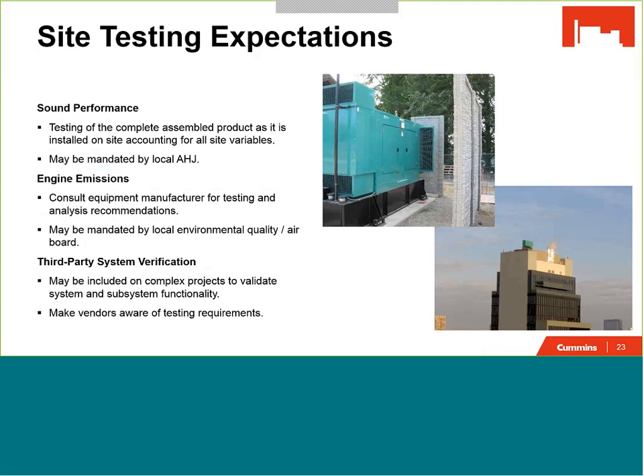Some other on-site testing expectations or types that we see include things like sound testing. Sound testing is often verified on-site if there is a local requirement from some local authority. The key here takes us back to our prototype testing point that we made earlier, in that the ability of a generator set manufacturer to promise or guarantee that they're going to meet your on-site requirements relies heavily on that prototype testing and its quality.